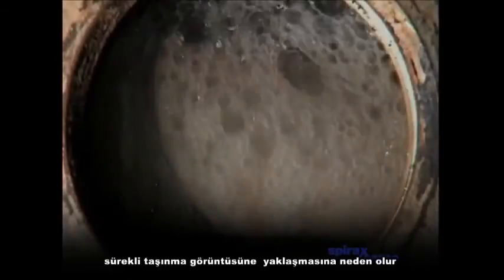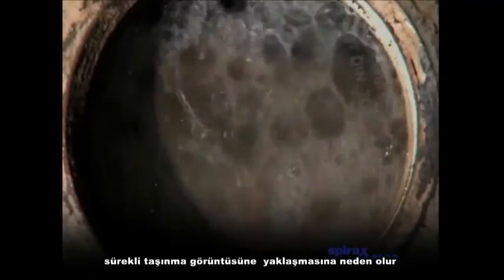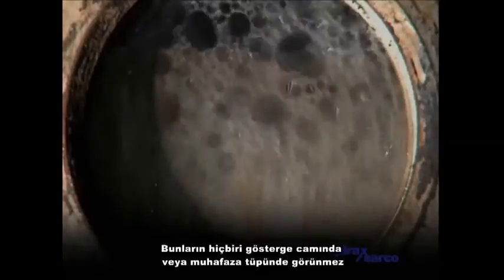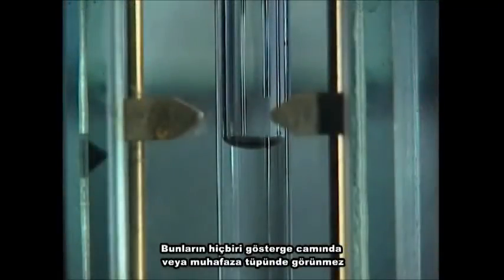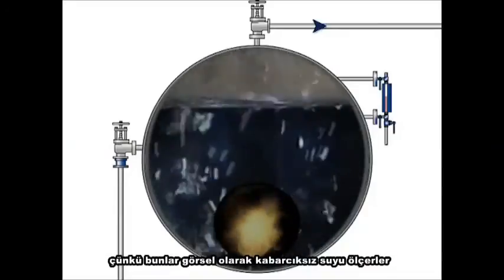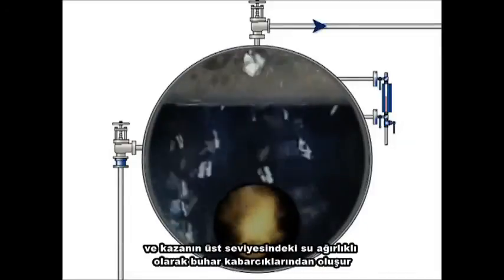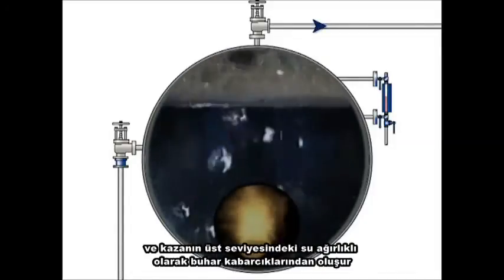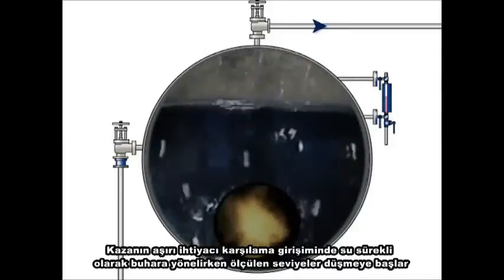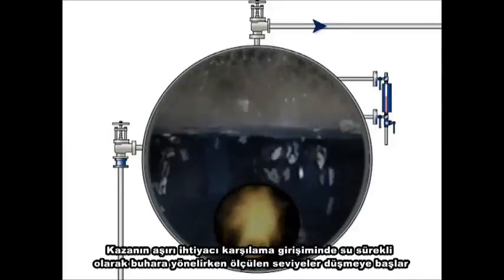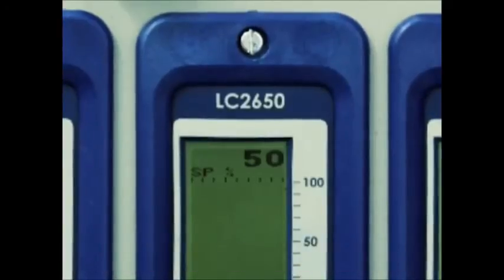Water is soon drawn into the steam takeoff, but this time without the demand moderating. The turbulent bubble level continues to rise, swamping the camera pod, leading to near-continuous carryover. None of this is apparent in the gauge glass or the protection tube, because they are measuring virtually bubble-free water, and the water at the top of the boiler consists mainly of steam bubbles. The measured levels begin to fall as water continuously flashes into steam in the boiler's attempt to satisfy the excessive demand. Eventually, the first low-level alarm is triggered.